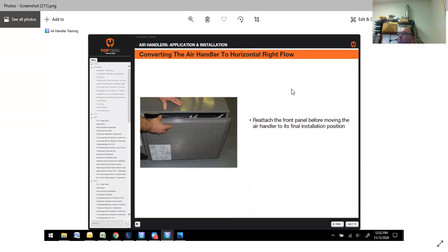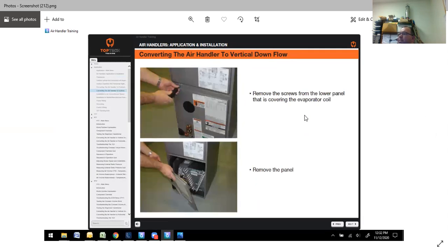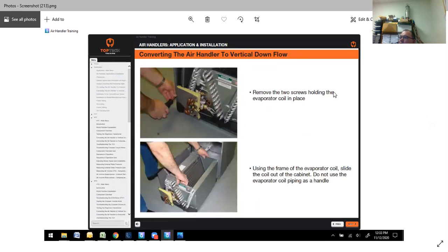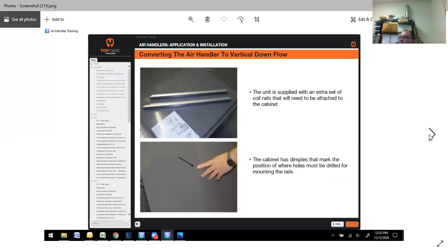So as you're converting the air handler to the horizontal right, reattach the front panel before moving the position to its final position. Remove the screws. This is for the vertical downflow here. Remove the screws from the lower panel that is covering the evaporator coil. Remove that panel. Remove the 2 screws holding it in place. There again, use the frame, not the actual piping, to pull it out.